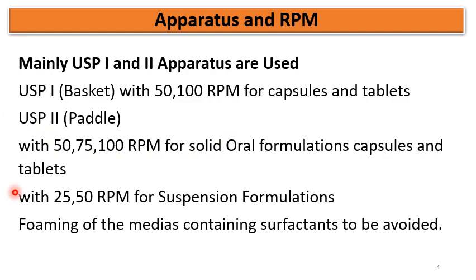Regarding RPM selection: when USP-1 basket apparatus is used, the RPM is generally kept at 50 or 100 RPM. USP-1 basket apparatus is mainly used for oral capsules and tablets. For USP-2 paddle apparatus, the RPM can be 50, 60, 75, or 100 RPM depending on the oral solid formulation. If heap or cone formation is observed at the bottom of the dissolution bowl, the RPM is increased. Generally, the standard RPM is 50 RPM.